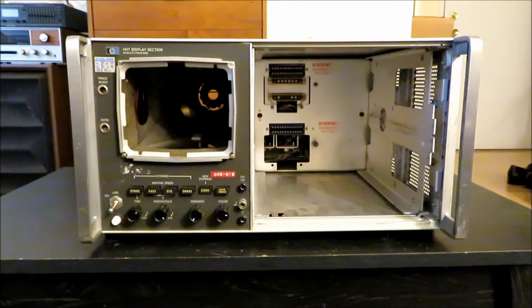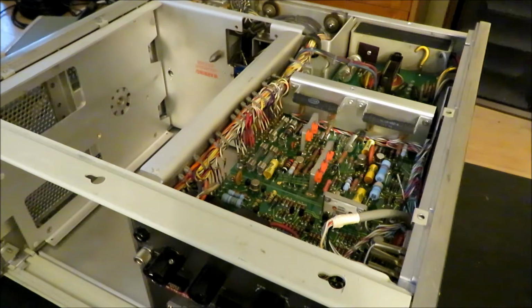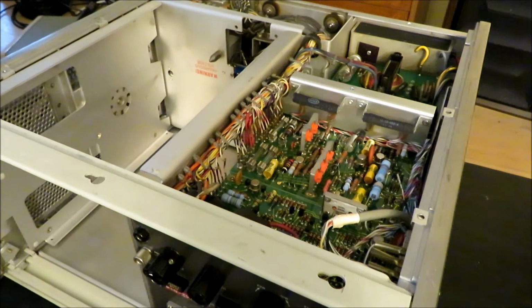So what we're going to need to do is turn the unit upside down and open up the high voltage section. So now we have the unit turned over and the bottom cover removed and also the high voltage cover removed. And the first thing we're going to want to do is turn off the high voltage oscillator. The two components specifically that we're going to want to remove are L1 and R57.